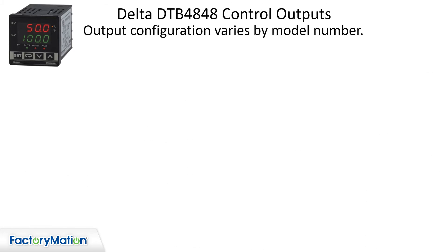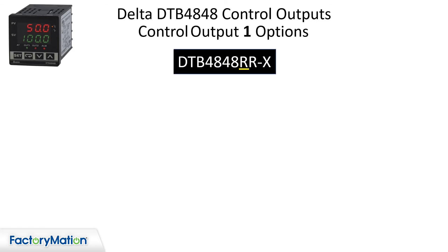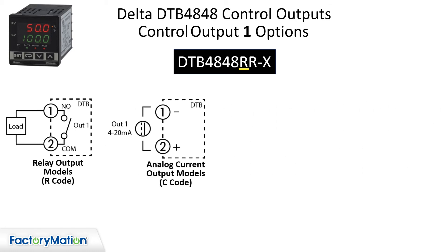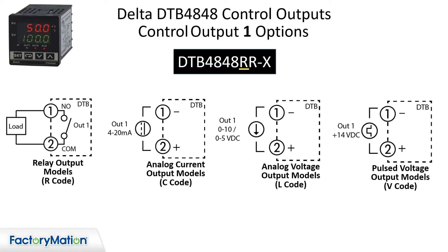Output configuration varies by model number. The first alpha character in the part number designates output 1. Output 1 can be a relay, analog current, analog voltage, or a 14-volt DC pulse output to drive a solid state relay.